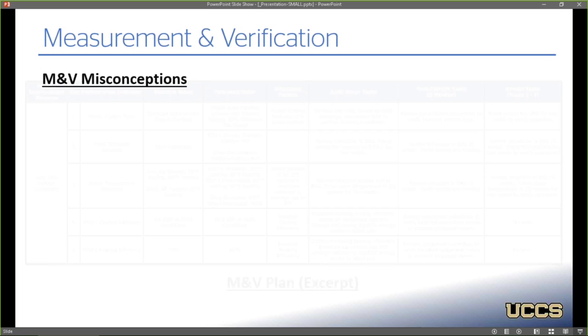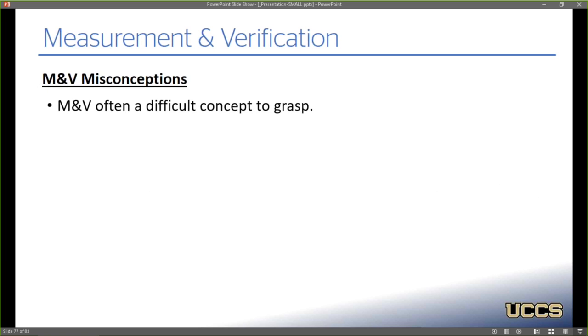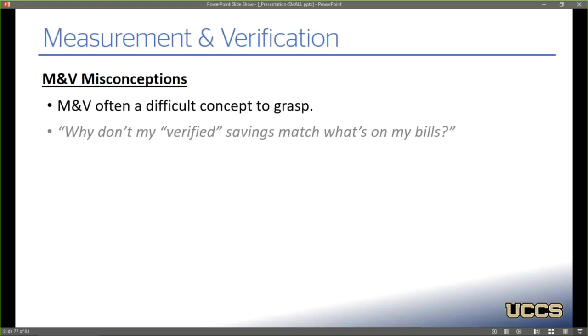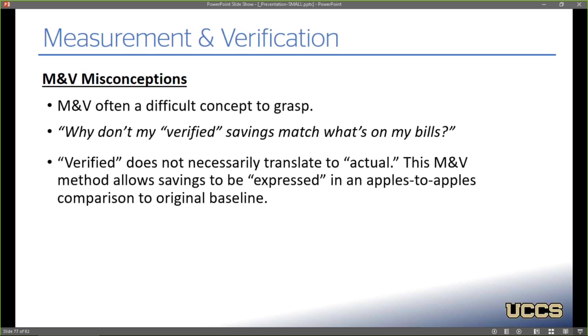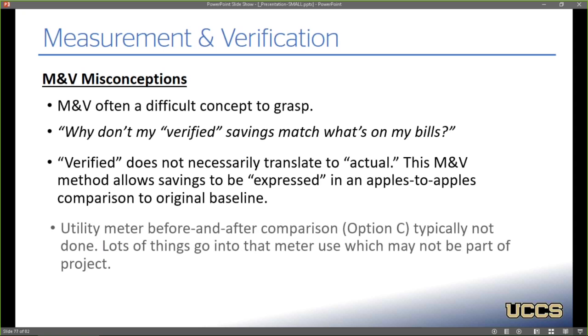And then annual tasks would be, what do we do at year 1, 2, or 3, or however long we pay for it? So some misconceptions is M&V is often hard to explain. People think we're looking at bills. Why don't my verified savings match what's on my bills? And verified doesn't necessarily translate to actual because of all these stipulated savings and weather changes and that sort of thing. So this M&V method allows savings to be expressed in an apples-to-apples comparison. So that option C of utility meter analysis is typically not done because lots of things go into that metered use that may not be part of the project that we actually did.